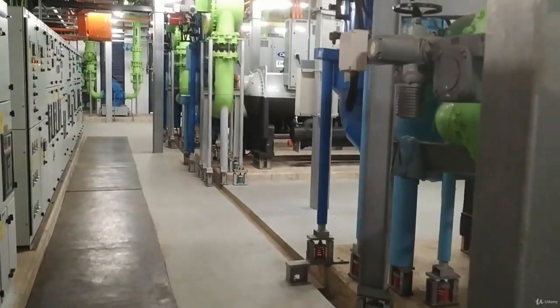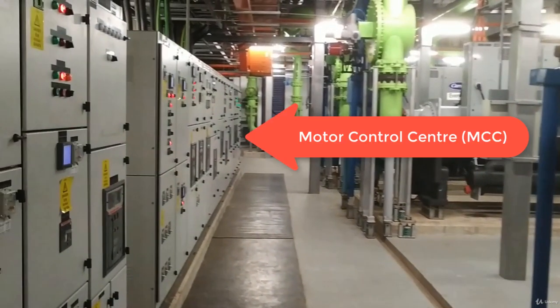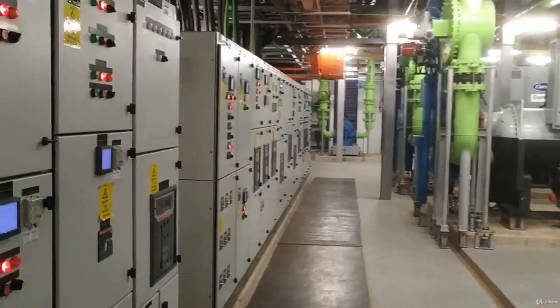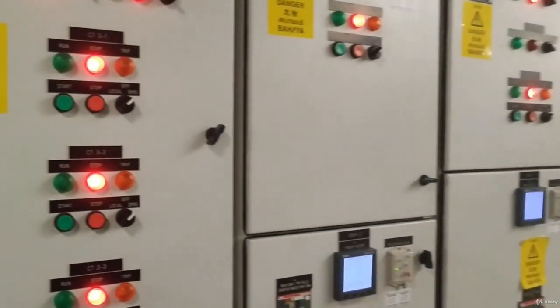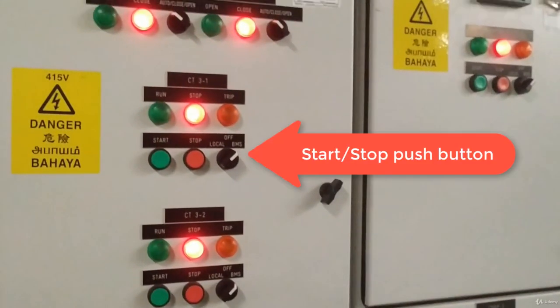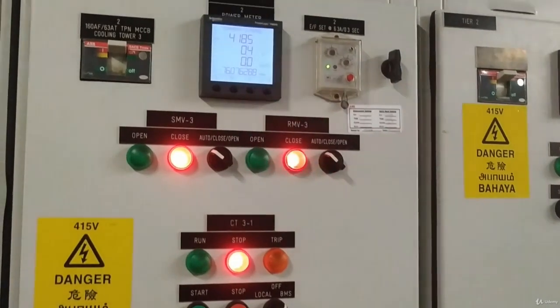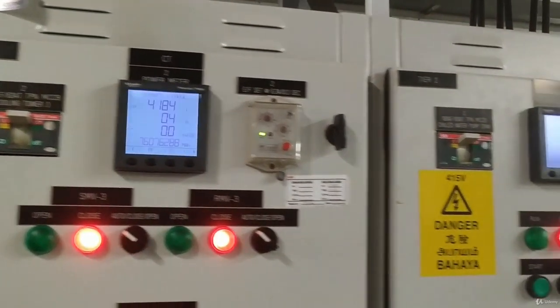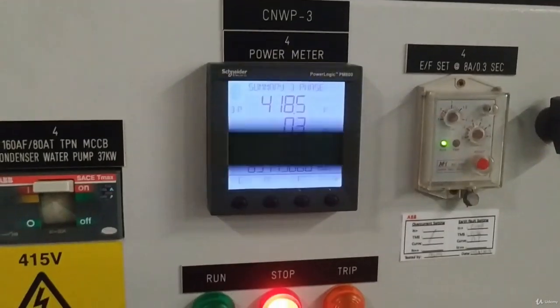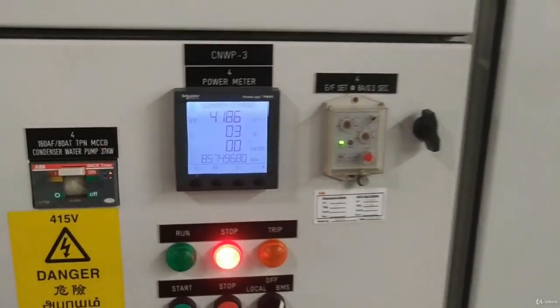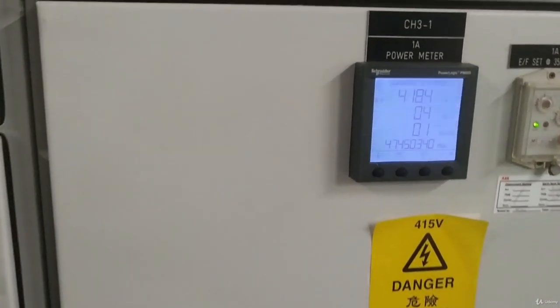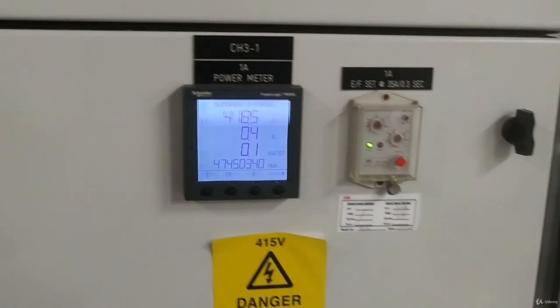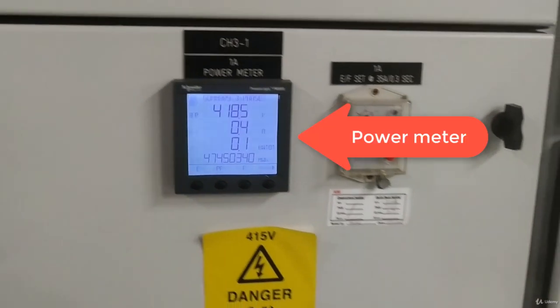These are the motor control centers. In short, we call it MCC. At the MCC, you can power on or off the various equipment manually, such as the chillers, pumps, and cooling towers. However, we seldom do that except during servicing and maintenance, as the start-stop controls of all these equipments are done through the BMS. And usually the power meters are attached to the MCC, and you can check the power, current or voltage reading from the panel over here.